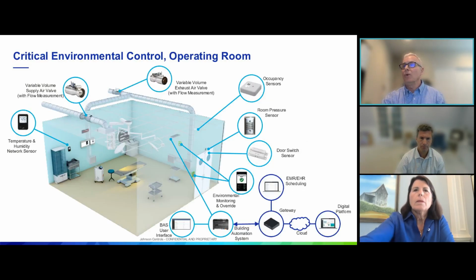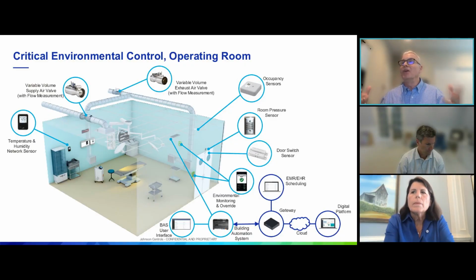So now we've got our underlying principles here, looking at that energy, looking at the compliance, looking at the performance. This is an artist rendition of an OR suite. When we look at this and start looking at how much data is available, we go through everything that we could possibly look at from that compliance standpoint, whether it's Joint Commission or some authority having jurisdiction. But how do we utilize that data? How do we control it? How do we make sure we're within those thresholds that ASHRAE 170 is requiring?